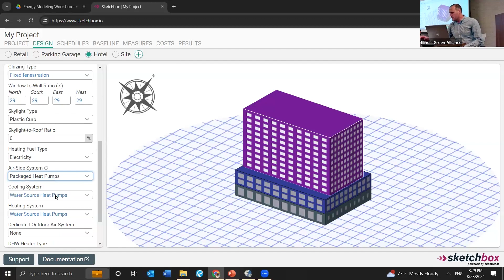Choosing none means you're bringing outside air in through the primary heating and cooling system you selected. If you choose a rooftop unit, that adds a gas-fired, DX-cooled, dedicated outside air unit supplying all the ventilation air for the building. If you choose same as primary HVAC system, it turns that DOAS unit into the closest match to your other system. So in this case, that'd be a water source heat pump. If you had a ground source heat pump, that'd be a ground source heat pump DOAS. If you had a gas-fired VAV system, it'd be a gas-fired VAV type DOAS.